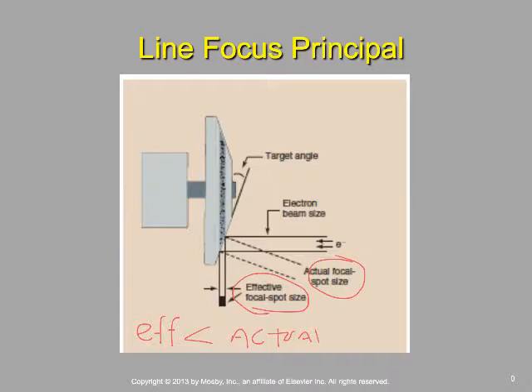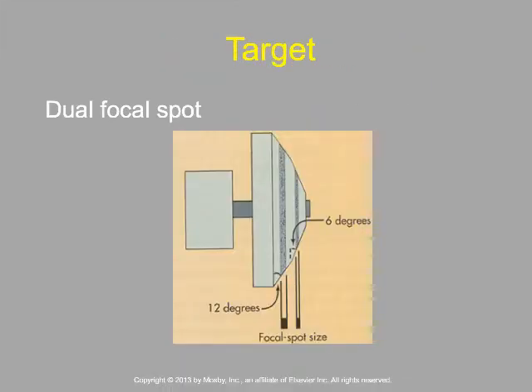The line focus principle produces an effective focal spot size much smaller than the actual focal spot. That filament originally maybe a half or one centimeter — the effective focal spot is going to be in millimeters. There are dual focal spots on the anode to match the dual filament sizes, with slightly different angles for each — perhaps a smaller degree angle for the small filament and a 12-degree angle for the large focal spot.